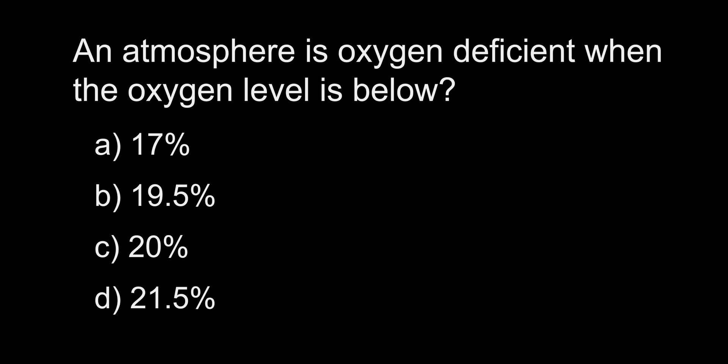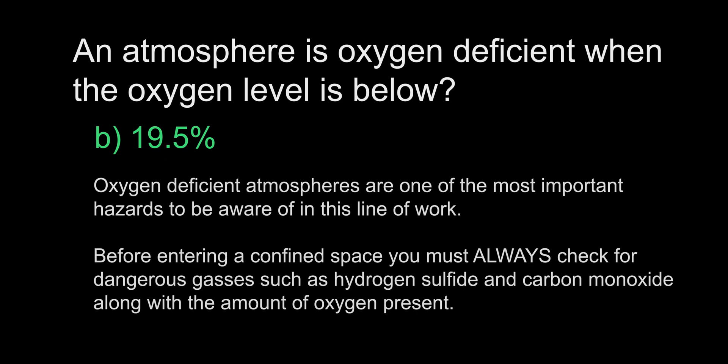An atmosphere is oxygen deficient when the oxygen level is below: A. 17%, B. 19.5%, C. 20%, D. 21.5%. The answer is B, 19.5%. OSHA has determined the optimal range for oxygen in the air for humans to be between 19.5% and 23.5%. Lack of oxygen or the presence of harmful gases such as hydrogen sulfide when entering confined spaces has taken many lives over the years. One must always check a confined space using a functioning and calibrated gas detector before entering, and a gas detector should remain with you while inside. There should also be someone outside the confined space who is responsible for monitoring the safety of those inside.